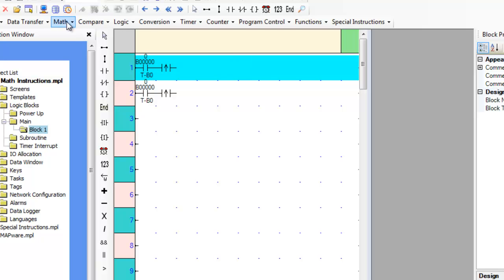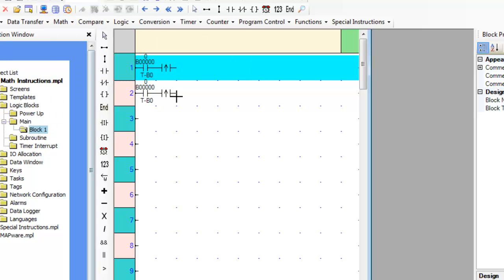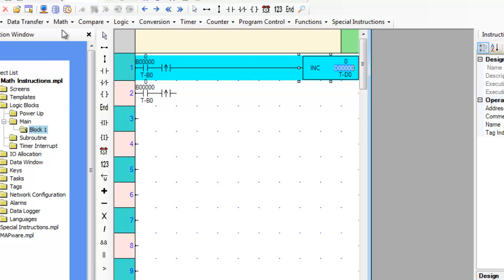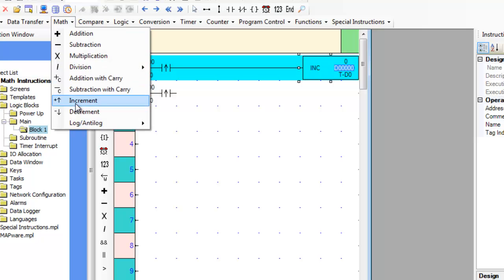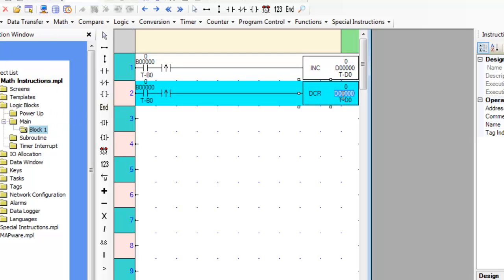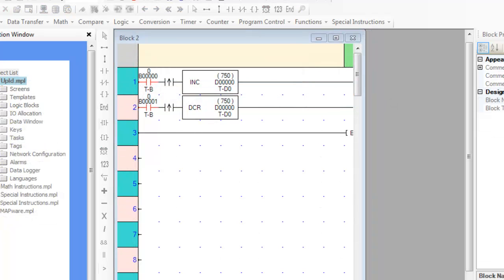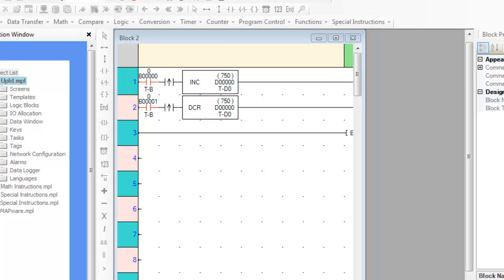The increment and decrement instructions will increase or decrease the value of the associated register by 1 each time the rung is true. If the register associated with an increment instruction has a value of 750 in it and the rung is true, the value will be increased to 751. Inversely, if the same register is associated with a decrement instruction and the rung becomes true, the value will decrease from 751 to 750.